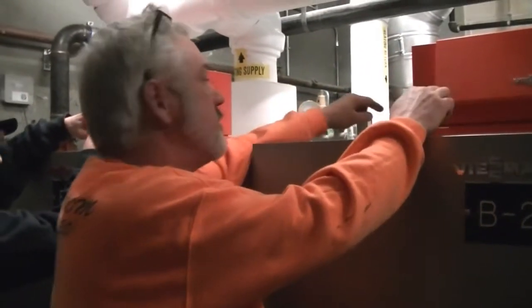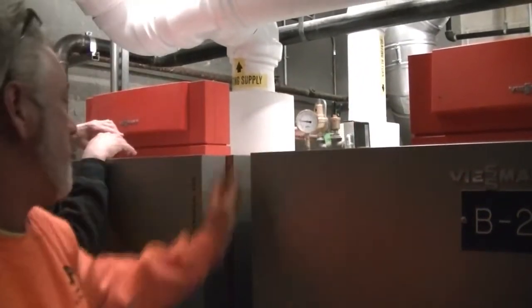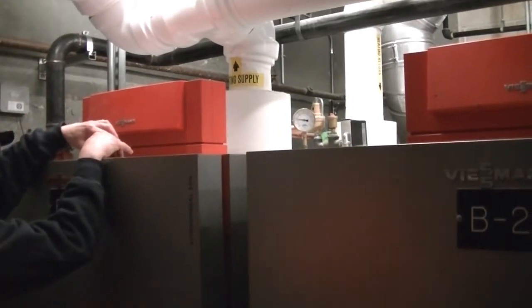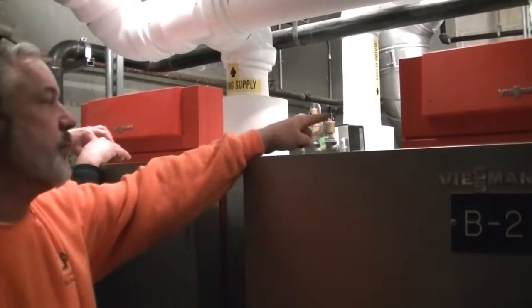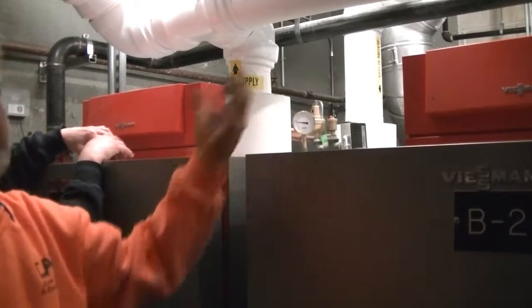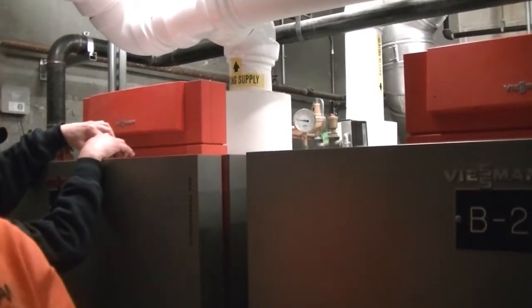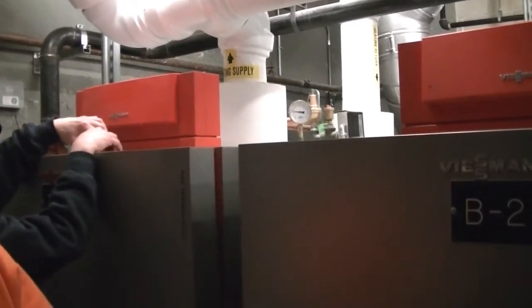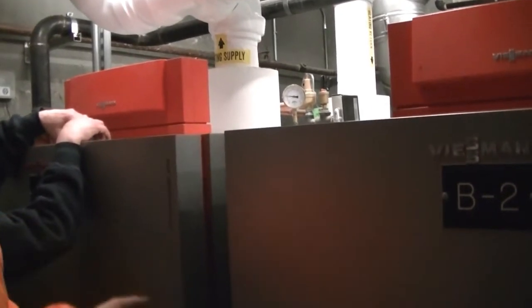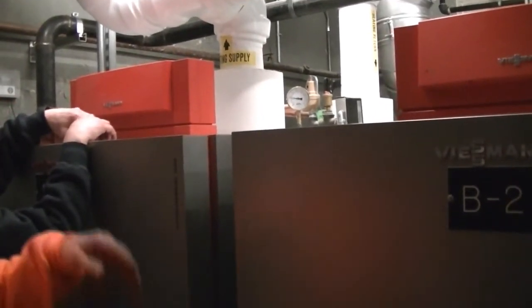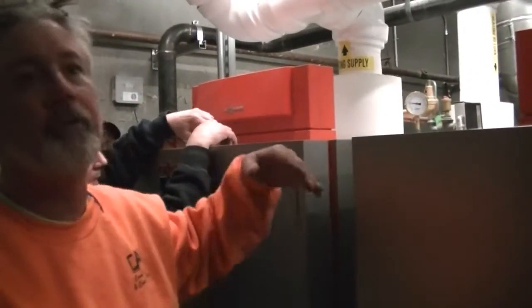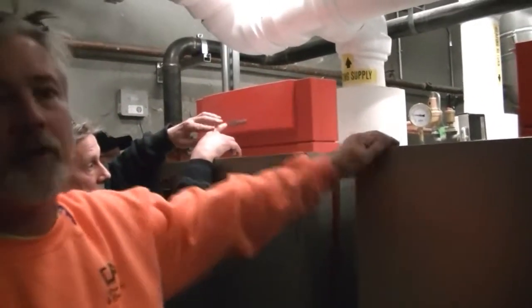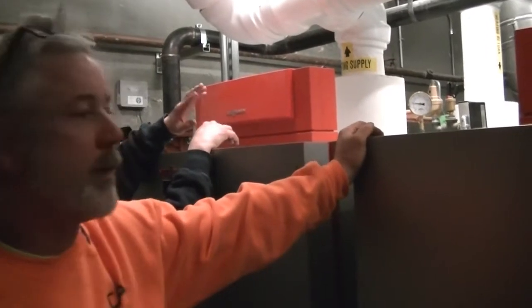Isolate the boiler at the top, 2 isolation valves. There's a boiler drain on the back of the boiler. Relieve the pressure on it. Then you can unscrew that vent, okay? Take the vent off, take it to a faucet, rinse it out, shake it out. You'll see mud coming out of it until we're done with the entire project. And then put it back on, open the valves, you'll hear it aspirate until all the air's gone. Refire the boiler and you should be fine, okay?